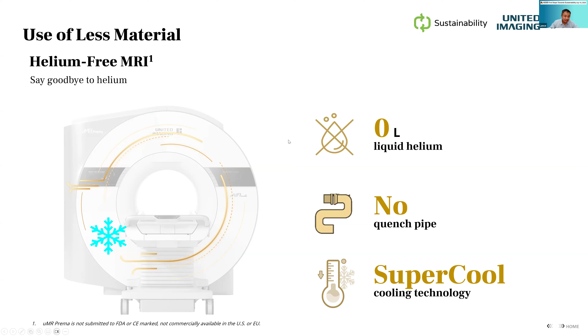Also, it's not only energy consumption, it's also material consumption. Traditionally, helium is one of the biggest materials that is consumed in every single magnet. Typically, an MR magnet consumes somewhere between 500 to 2,000 liters of helium. And by introducing the latest technology with better cooling to the magnet as well as high temperature superconducting, we can minimize the use of liquid helium and also achieve significant cost saving and material saving for the MRI business.